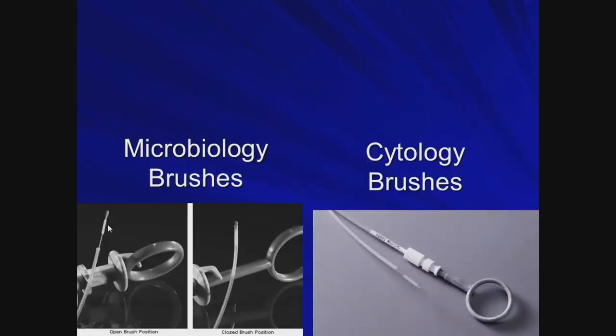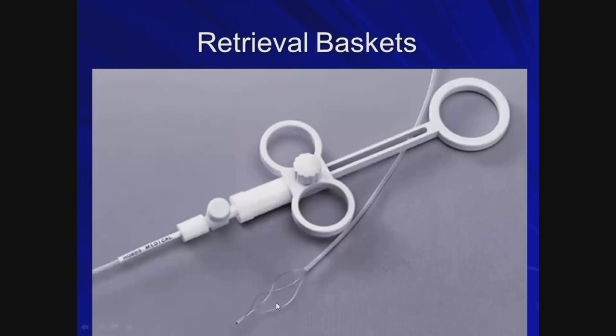Brushes for cytology: the brush is recessed within a protective casing so you can brush tissue and retract it back inside to prevent contamination as you pull it back out. These are used for cytology and tissue sampling. Retrieval baskets are used for aspirated objects further down that the rigid bronchoscope can't access — you slide the basket around the object and pull back to close the basket down and retrieve it.